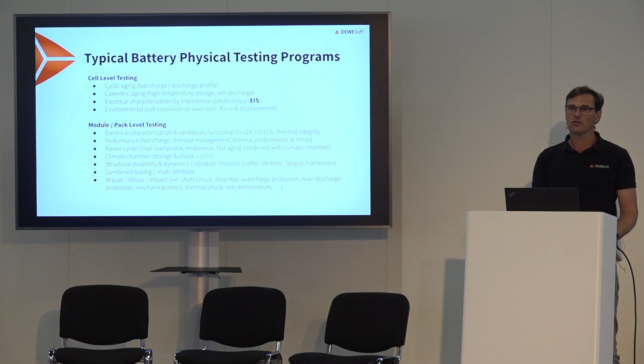I took the short circuit test first because I'm a big fan of it—it's so exciting. This means you basically have an external short circuit, and you can test it with the pyrofuses inside the junction box, checking if they're working, whether there's actually a disconnect between the short circuit and the battery so it doesn't go to thermal runaway, or you test without the pyrofuses, without the disconnect, which in that case can mean a really serious fire at the end.